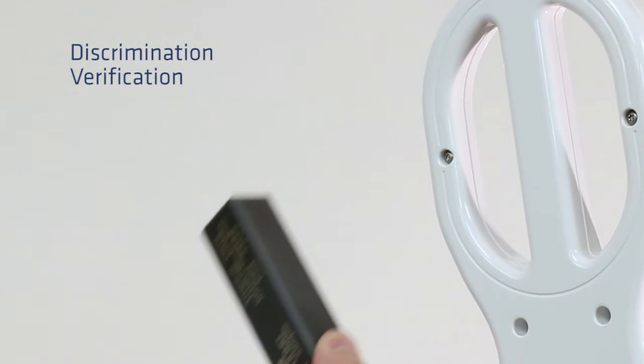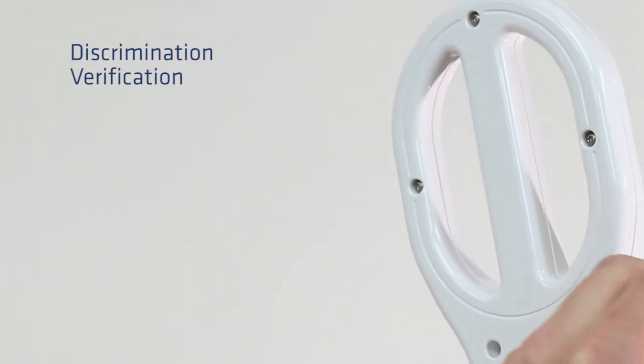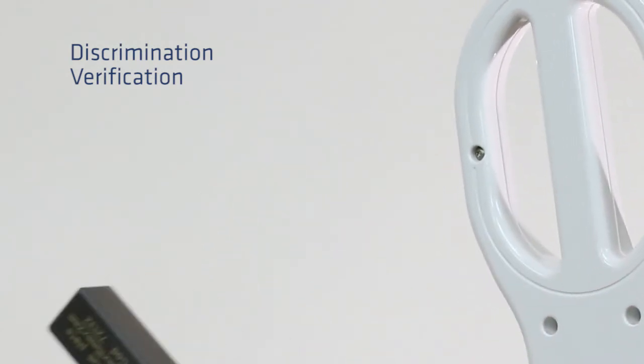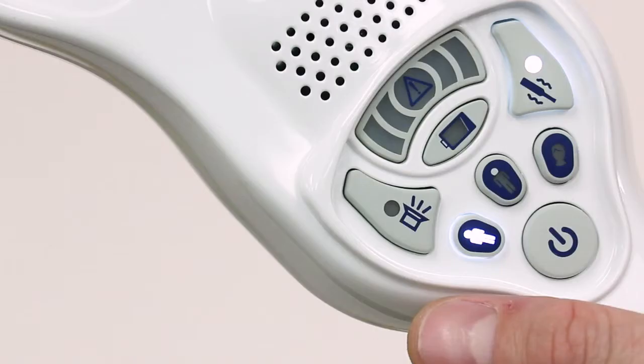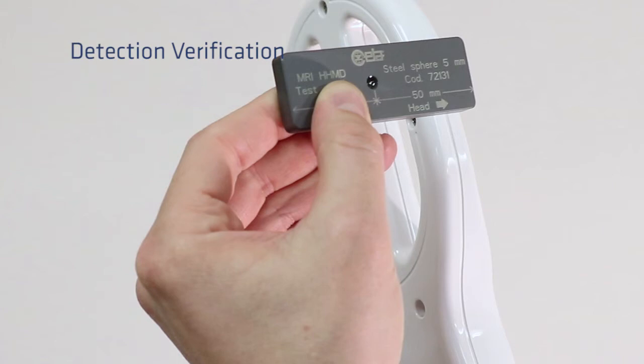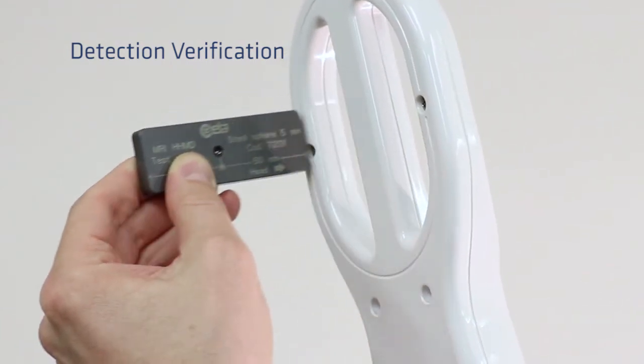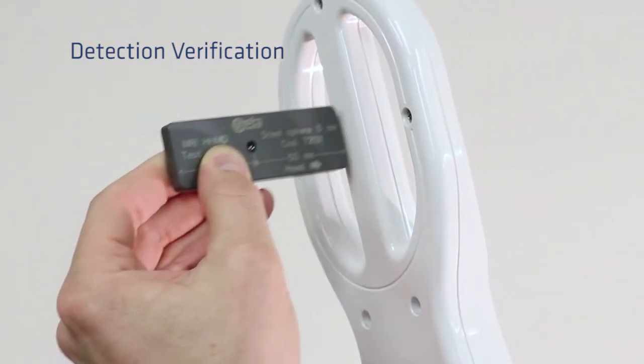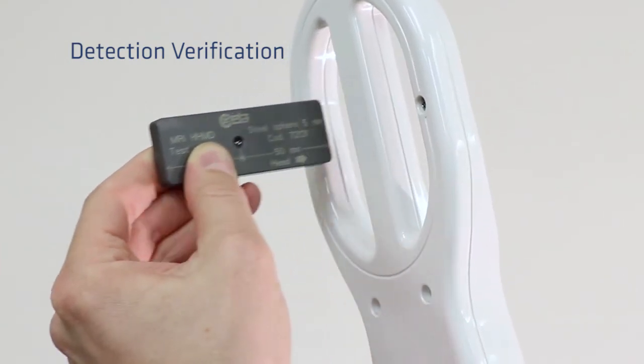Then pass the titanium plate discrimination test piece close to the bottom side of the detector. Make sure the test piece passes over the center point of the sensing area and that it does not trigger an alarm. Select All Metals Analysis Mode. Then pass the steel sphere detection test piece close to the bottom side of the detector with the arrow for head pointing towards the device. Make sure the test piece passes over the center point of the sensing area and that it triggers an alarm.